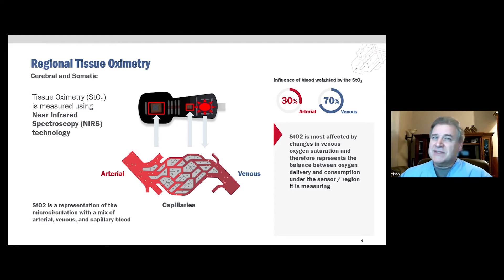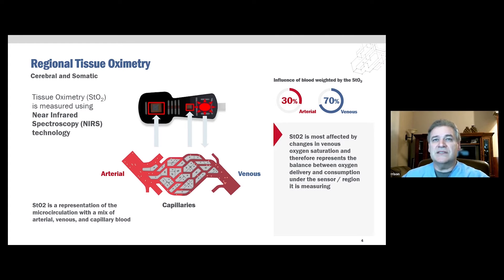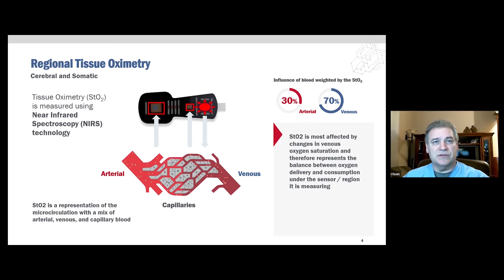For those who are not familiar with NIRS tissue oximetry in general, in a nutshell, it utilizes near-infrared spectroscopy to assess the oxygen saturation of vascular beds underneath a self-adhesive sensor that is applied to the skin and interrogates up to 2.5 centimeters beneath the sensor. Since the measured values are most affected by changes in the venous oxygen saturations, these values represent a mechanism to evaluate the DO2-VO2 relationship.